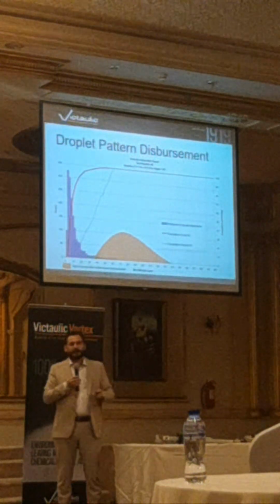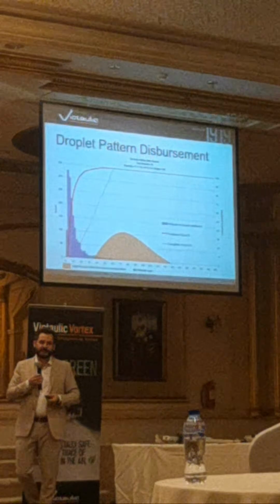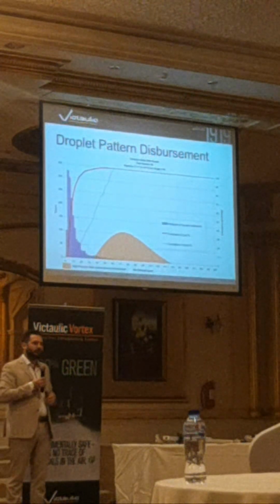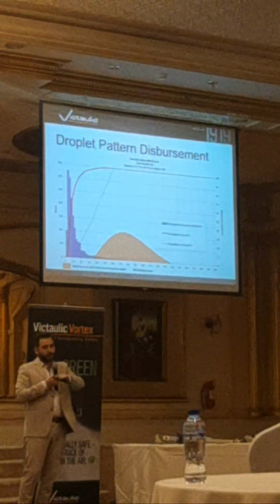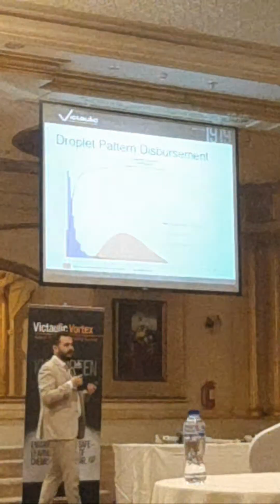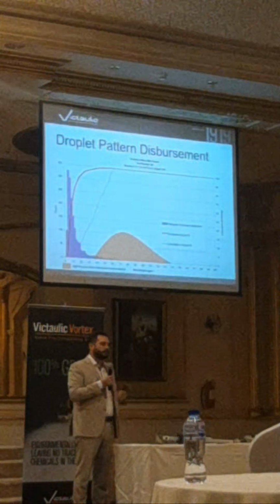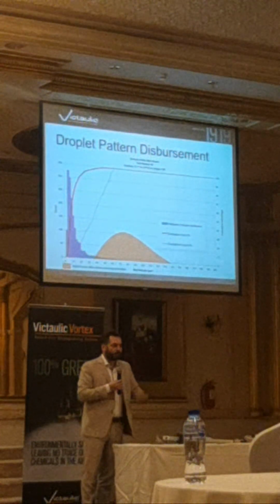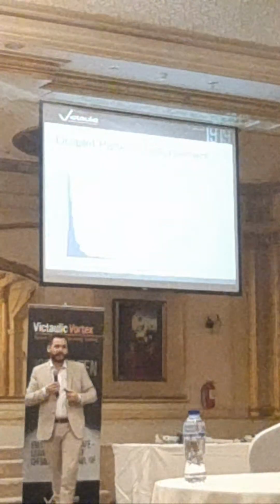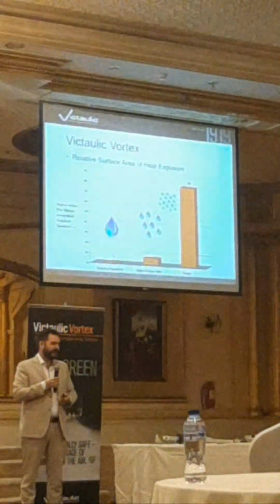As a comparison, we have added the high pressure water mist, indicated in brown orange. You can see that with the water mist you're going to have a longer draft, and also the amount of droplets is going to be lower. This means that water mist needs to add much more water compared to vortex. It all has to do with the relative surface area of heat exposure.